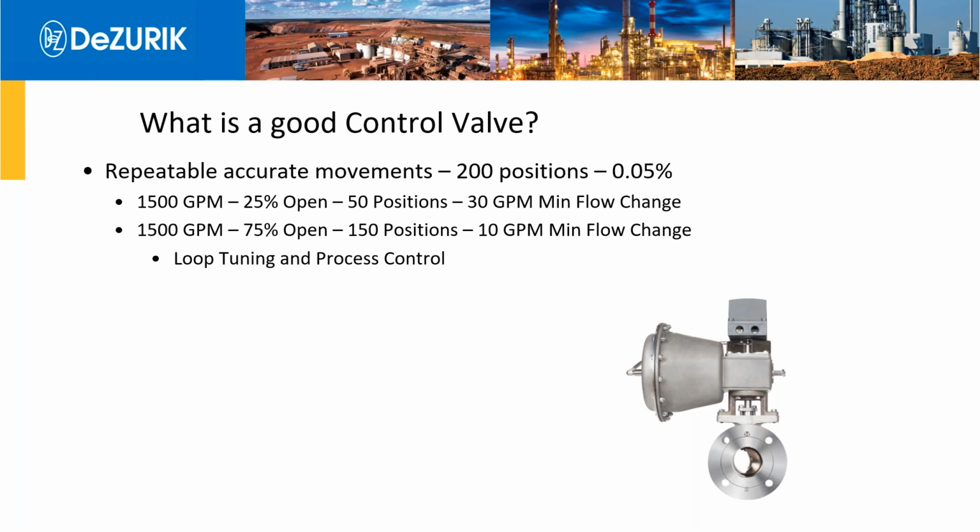Analogy I like to use is cruise control on a car. If you would set your cruise control at a certain miles per hour, every time you hit the advance or the decrease button, it moves up or down 1 mile per hour. Well, if that button would move the speed of the car up or down 5 miles per hour, it would not be acceptable performance. We've done a lot of studies of control valves in loops, and we found that the movement of the valve, or the smallest attainable movement, is a major contributor to loop instability.